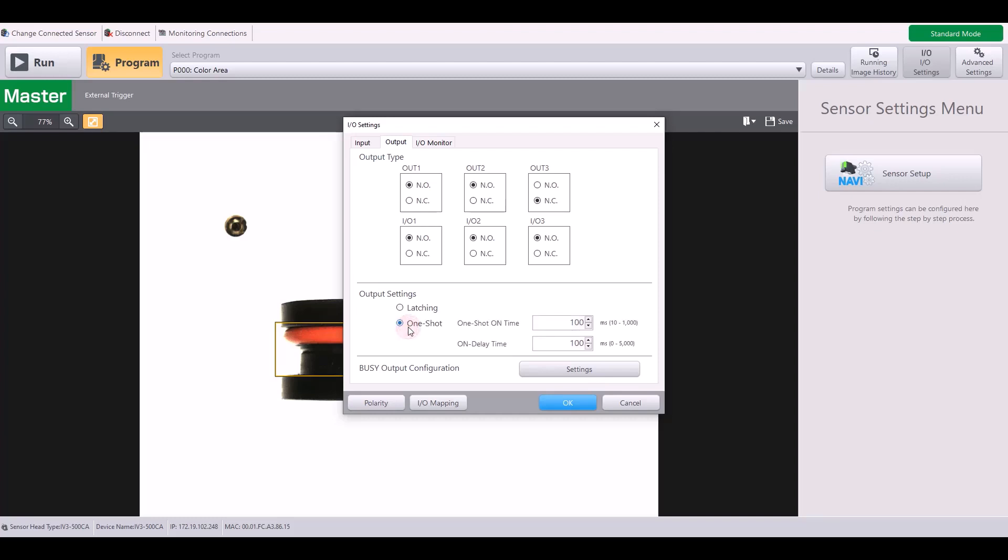However, if you want to hold it on for a specified amount of time, you can enable the one-shot here. Once you enable a one-shot, simply set your one-shot on time anywhere from 10 to 1,000 milliseconds. This will be how long that signal is held before it turns off. And then you can also set your on delay time, which is just the delay for when that signal turns on.